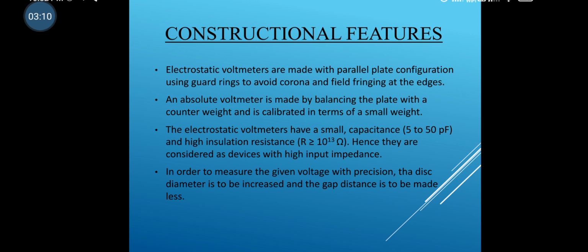Electrostatic voltmeters are usually made up of a parallel plate configuration using guarding and field fringing. An absolute voltmeter is made by balancing the plate with a counterweight and is calibrated in terms of small weight. The electrostatic voltmeter has a small capacitance ranging between 5 to 50 picofarad and high insulation resistance, that is greater than 10 to the power 13 ohm. Hence, electrostatic voltmeters are considered a device with high input impedance. In order to measure the given voltage with precision, the disc diameter is to be increased and the gap distance is to be made less.